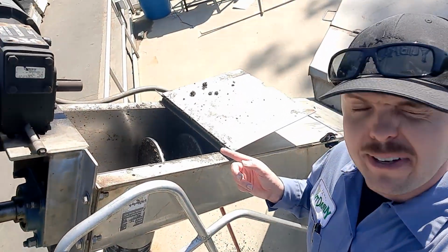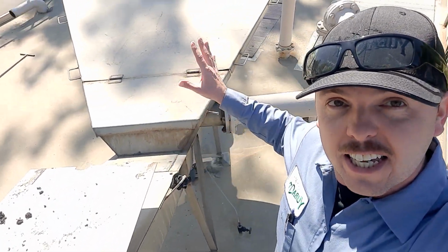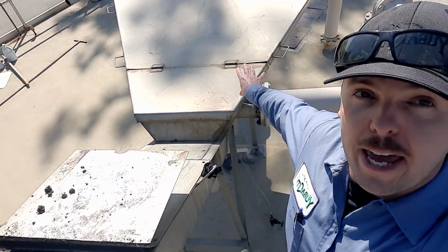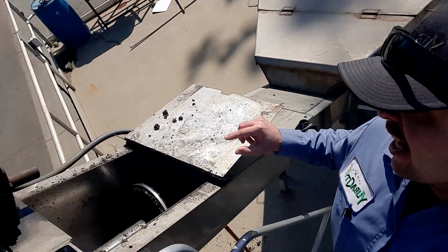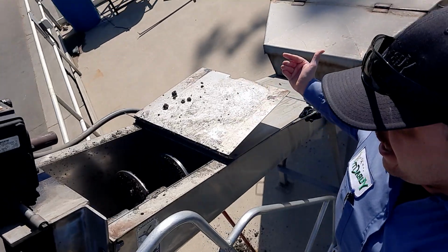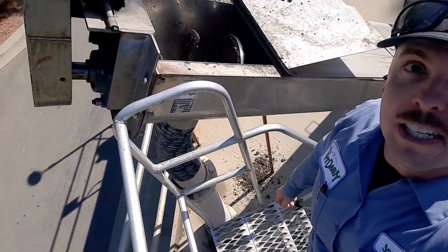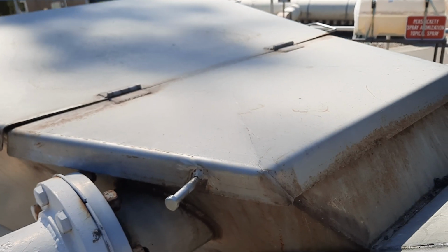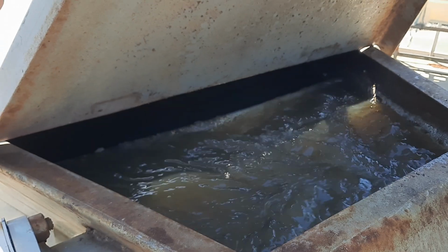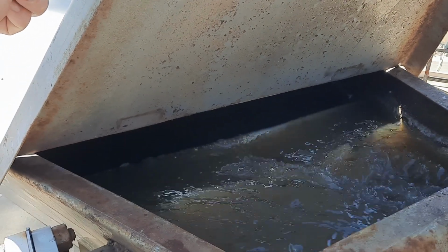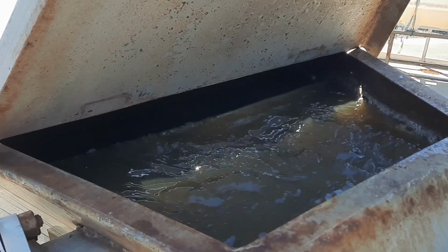You may be able to see behind me, but we call this guy an auger. And basically all the grit and some water too is going to be pumped into this guy. It's all going to sink to the bottom. This auger is going to catch the grit and move it and pump it down into that pipe where we're going to bag it and send it to the landfill, in case anybody's wondering. So that's it going in. It's got a baffle right behind it to make sure we don't, quote unquote, short circuit and send any grit back into the process.